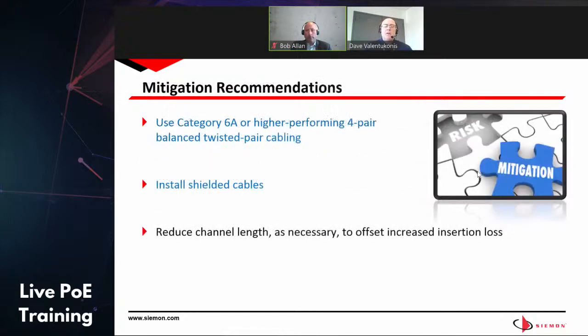The mitigation recommendations for managing remote powering are actually kind of simple. It's a twofold approach. You use the largest conductors you can, which in North America is category 6A or higher. There's category 8 cable, but that's really a limited application use. Category 7A is something you could use in North America that's a larger gauge, like 23, 22 gauge. And then install shielded cables. If you don't do that, you have to reduce your overall channel length. So if you put those two together, the message is category 6A shielded cabling is the best you can do for managing remote powering as per North American standards.